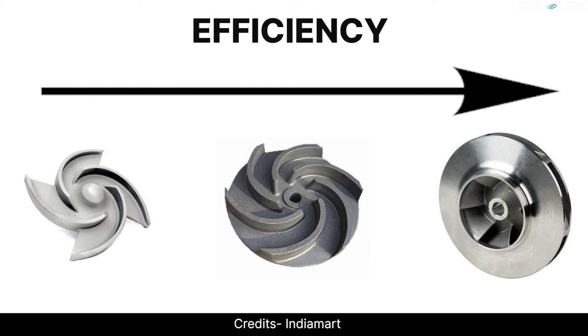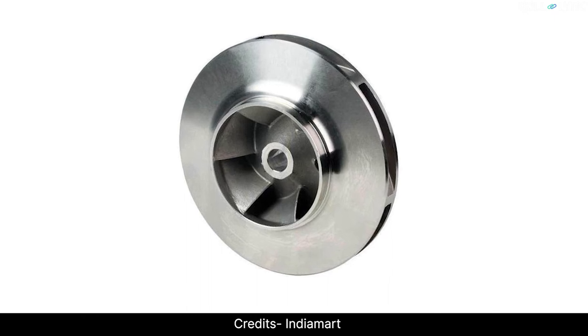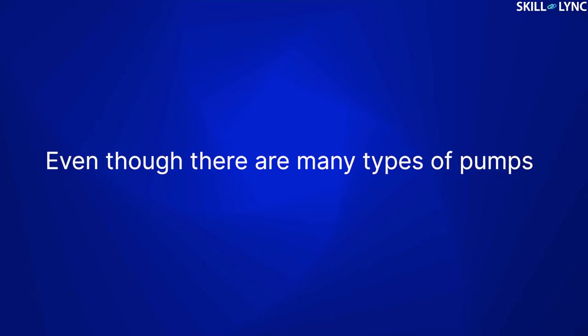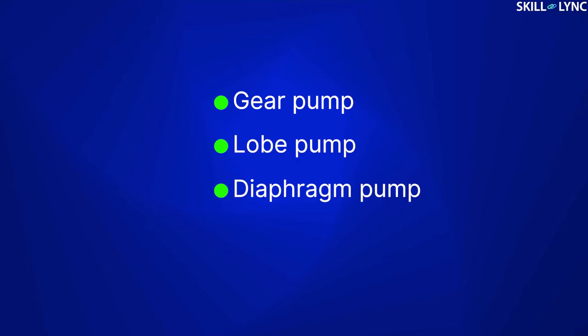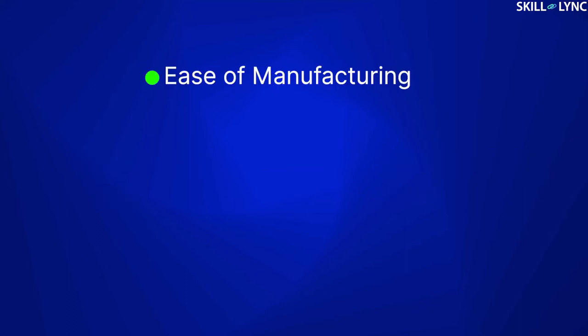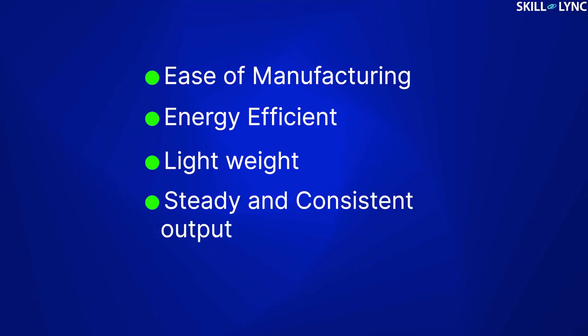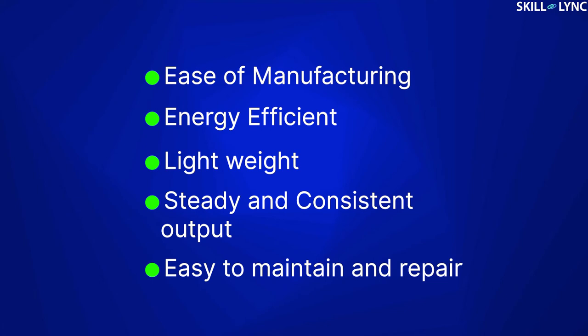However, open type impellers are inefficient when compared to closed type impellers. Majority of domestic motors use a centrifugal pump with a closed type impeller. Even though there are many types of pumps like gear pump, lobe pump, diaphragm pump, screw pump, etc., the centrifugal pump is the most commonly used. The main reason is ease of manufacturing. These pumps are also energy efficient and lightweight, with steady and consistent output. They are also very easy to maintain and repair.